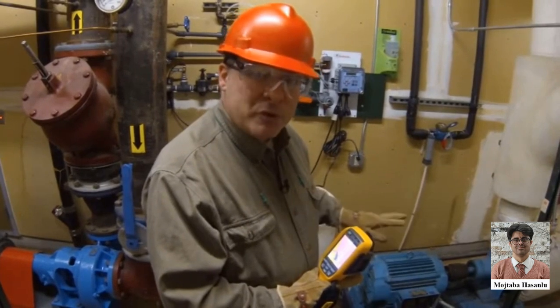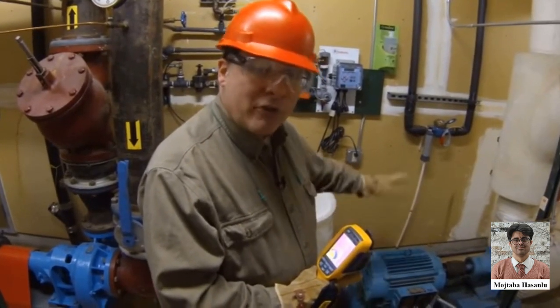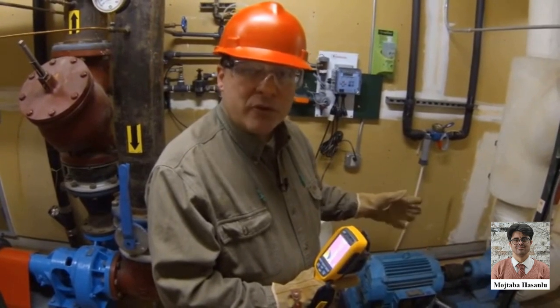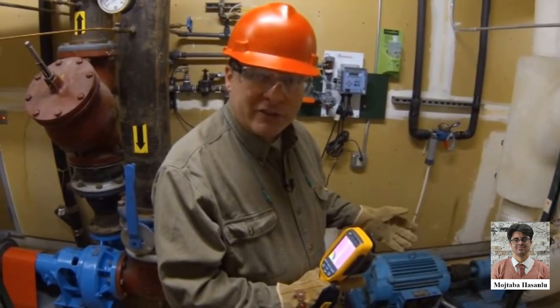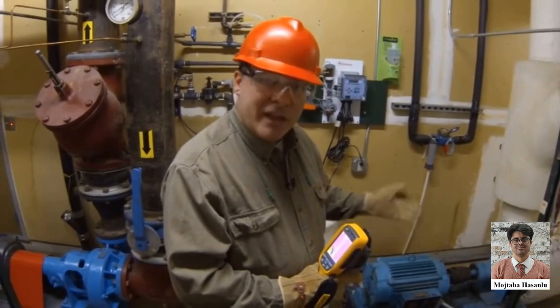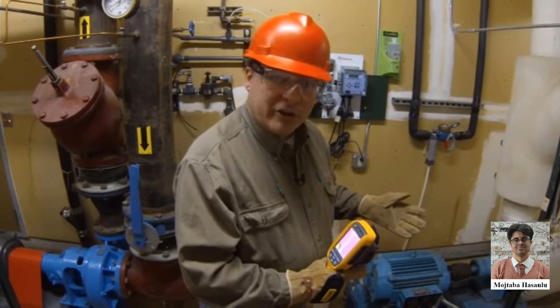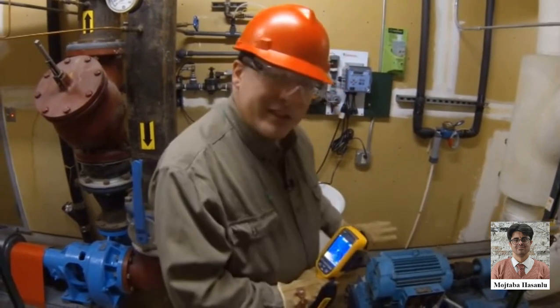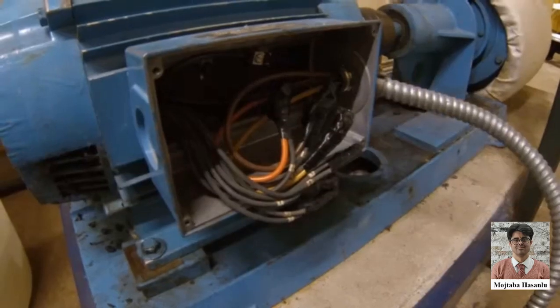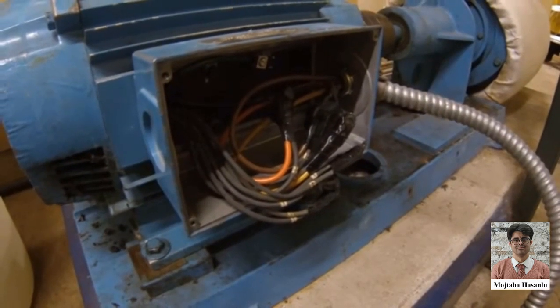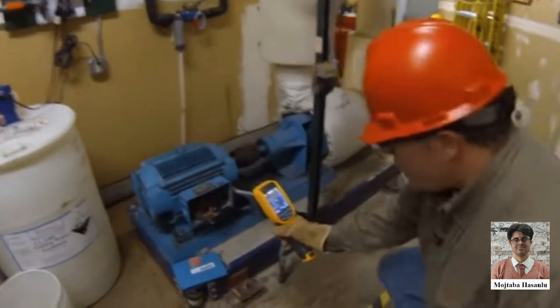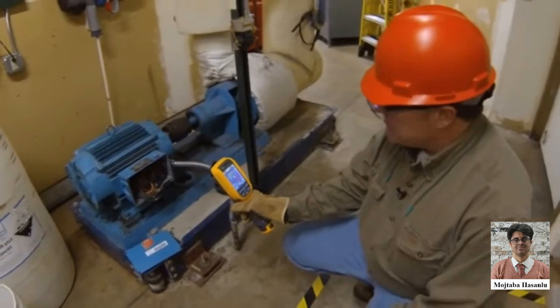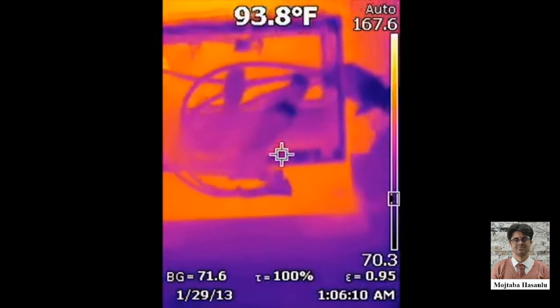Either one of these situations, the overall overheating or the localized overheating, can cause that motor to work a little bit harder than it needs to. It will draw more current in order to compensate for the problems that it has, and that will impact your bottom line and your energy usage. Next thing that I'll move on to is the electrical itself here in the termination box. I'll look for high resistance connections. So I'm not seeing anything here, but if I were to see a high resistance connection.